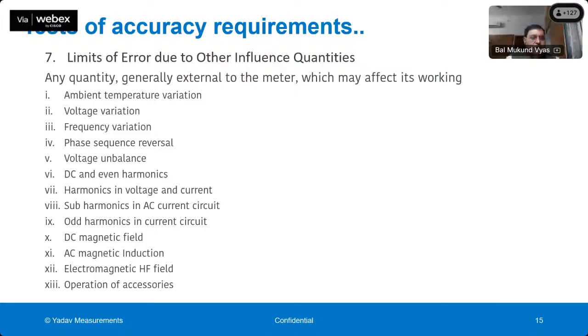Voltage unbalance. As voltage can vary, if it is a three-phase meter, voltage unbalance can also happen. So in one phase you have 250 volt, in another phase you have 200 volt, and in the third phase maybe you have 220 volts. This is all voltage unbalance. Under these voltage unbalance conditions, the meter's accuracy should not get affected beyond the limit.